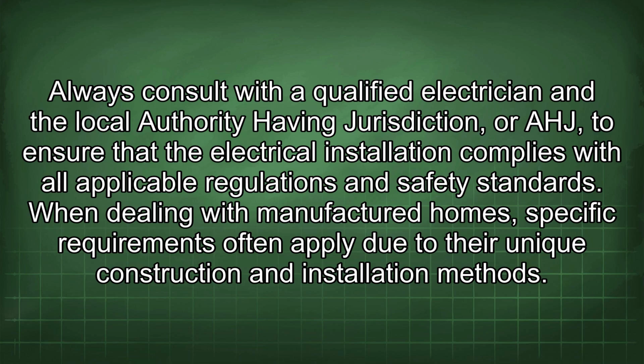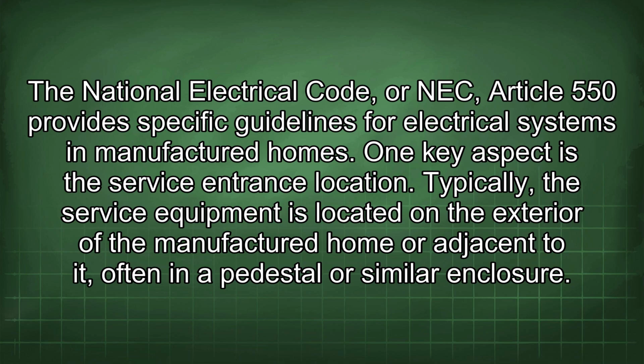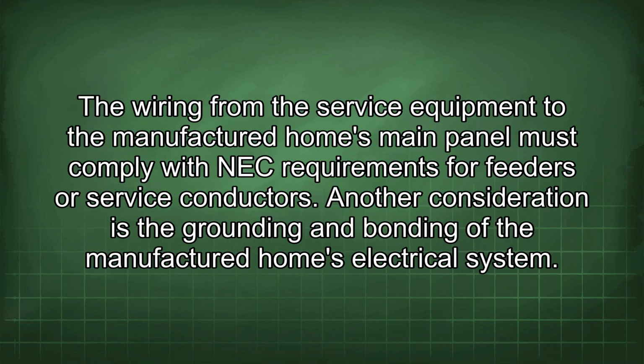When dealing with manufactured homes, specific requirements often apply due to their unique construction and installation methods. The National Electrical Code, or NEC, Article 550 provides specific guidelines for electrical systems in manufactured homes. One key aspect is the service entrance location. Typically, the service equipment is located on the exterior of the manufactured home or adjacent to it, often in a pedestal or similar enclosure. The wiring from the service equipment to the manufactured home's main panel must comply with NEC requirements for feeders or service conductors.